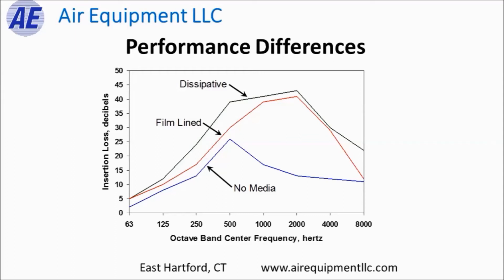The left-hand vertical column shows insertion loss in decibels — how much noise energy is absorbed from the airstream as it passes through the silencer. The higher the number, the better it's working. The dissipative silencer attenuates the most noise energy across the spectrum at every frequency. The film-lined type still attenuates a fair amount but not quite as much. The no media silencer attenuates the least. It's critical to analyze the entire application to select the right silencer that will achieve your target noise level in the space.